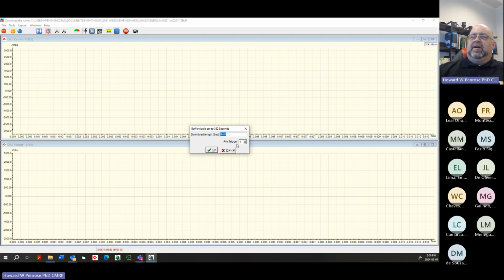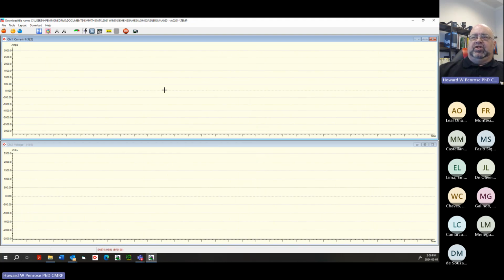And the pre-trigger, so once it hits that 500 amps, it'll collect data from 1 second before it hits that. I can change that value if I want. This is basically what we call inrush data. It will only show certain things. I don't do it normally unless I'm looking for problems on startup.